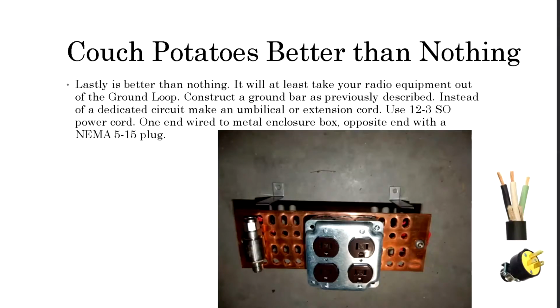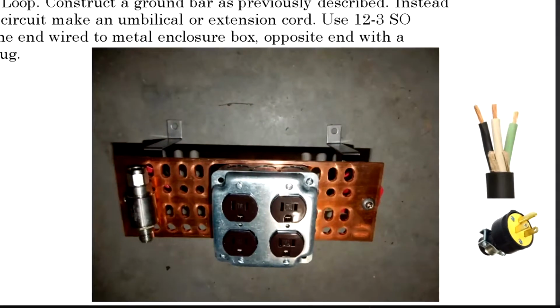Well, there is a third option for our couch potato friends out there, and it's at least better than nothing. The mock-up you see below is the station ground bar with the AC outlet and the surge protector on it, or the coax surge protector. Instead of bringing your dedicated AC circuit right into the back of that bus bar with your coax, you make yourself an umbilical cord using SO 12-3 cord and a NEMA 5-15 plug.